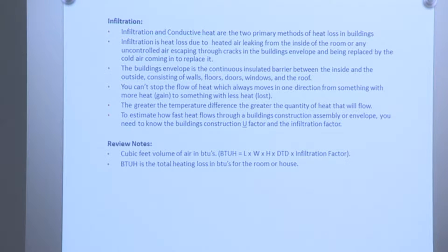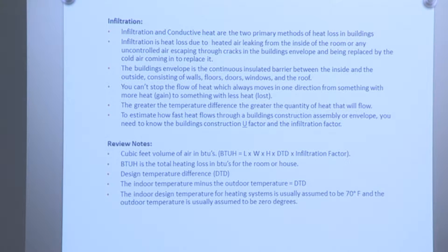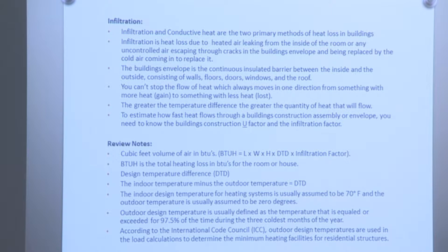BTUH is the total heating loss in BTUs for the room or house. Design temperature difference is DTD. The indoor temperature minus the outdoor temperature equals DDT. The indoor design temperature for a heating system is usually assumed to be 70 degrees Fahrenheit, and the outdoor temperature is usually assumed to be 0 degrees. Outdoor design temperature is usually defined as a temperature that is equaled or exceeded 97.5% of the time during the three coldest months of the year. According to the International Code Council, outdoor design temperatures are used in load calculations to determine the minimum heating facilities for residential structures.